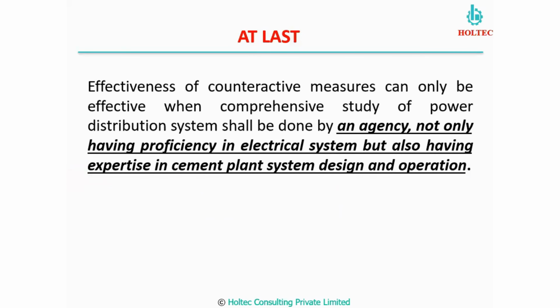Lastly, any corrective measure, that means an ILMS system or a study which we do, will be effective only when it is done by an agency which has not only proficiency in electrical power distribution but also expertise in your plant system design and operation, because the operation and electrical power distribution have to vary with each other. An agency which does not have knowledge of your plant processes cannot give you a proper design of the ILMS system. They cannot offer you an optimized integrated load management system, and cannot analyze through ETAP studies the various aspects of the power distribution, like load flow, short circuit, relay coordination, and transient, etc.